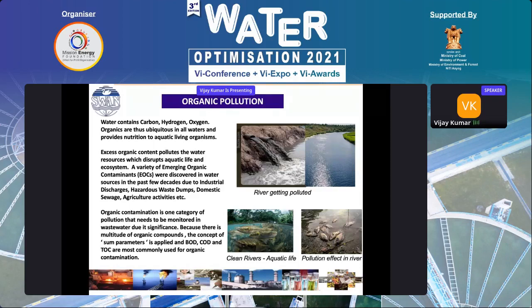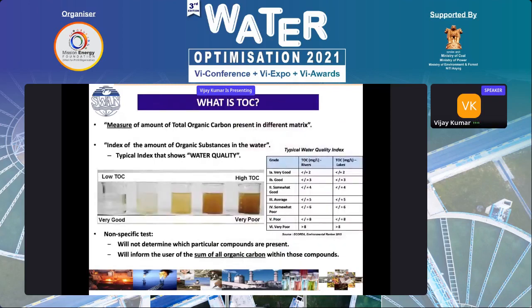So we define one parameter, based on either conventional methods like BOD, COD, and TOC. These are normal parameters we come across. What is TOC? It is the measurement of total organic carbon present in different matrices, an index of the amount of organic substance in the water. Typically, the index shows the water quality: very low is very good, very high is very poor. There was one magazine I've seen in Korea that gives a water quality index based on TOC. Almost 7 categories of water, between 2 ppm and 8 ppm.